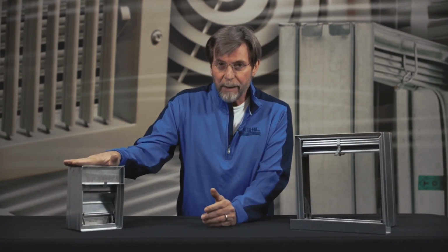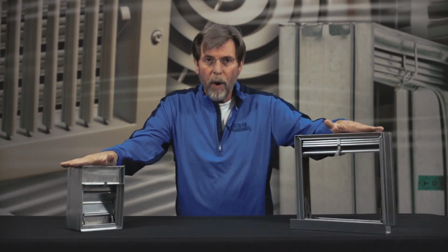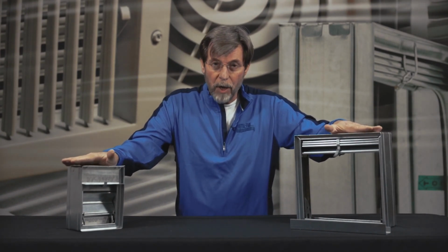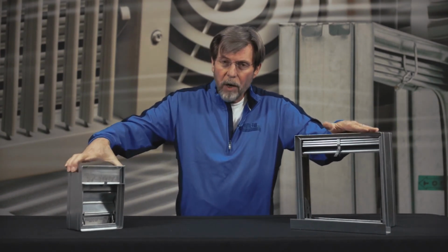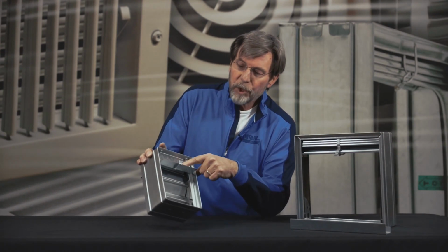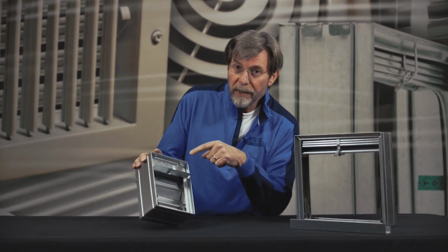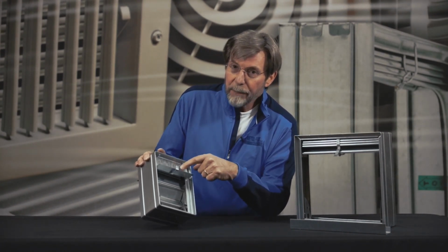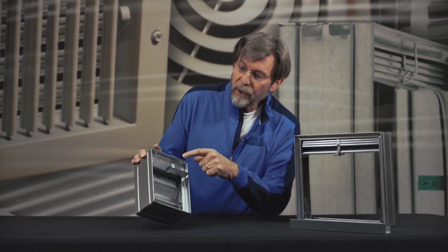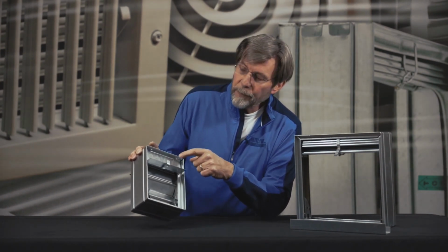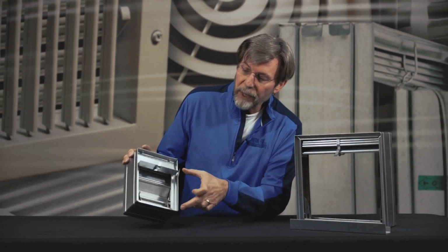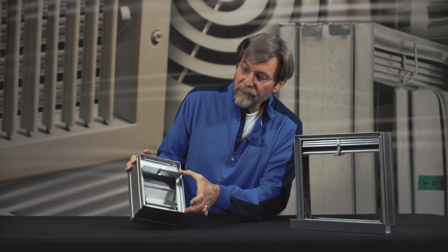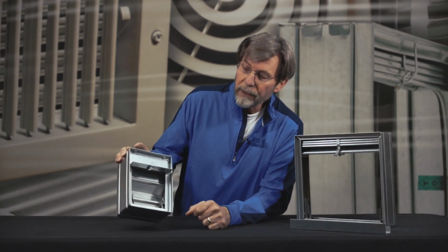Let's move on. So now we're looking at a type B damper, and you may be asking yourself, why do I still have a type A damper on display here? I'm going to show you. On our type B damper, I have a B channel. And where I was telling you about the type A damper and the blade stack being in the airstream, you can see here when they put this B channel on, it removes the blade stack from the airstream. The duct connection now will be with the frame and the bottom of this B channel that we see right there.